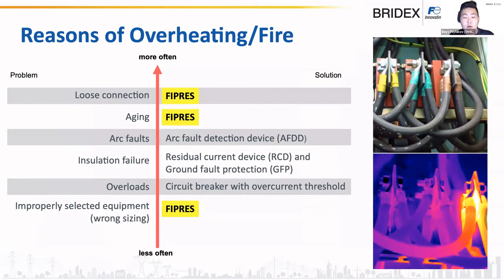So here you can see the list of typical reasons of overheating and further fire. On the left side, you can see the list of problems, and the list of solutions. This list is sorted by frequency. You can see here that the loose connection is the most frequent cause which can lead to a fire, and wrong sizing of cables or bus bars is the least frequent.